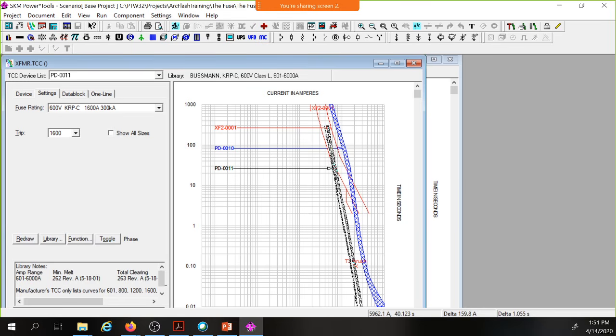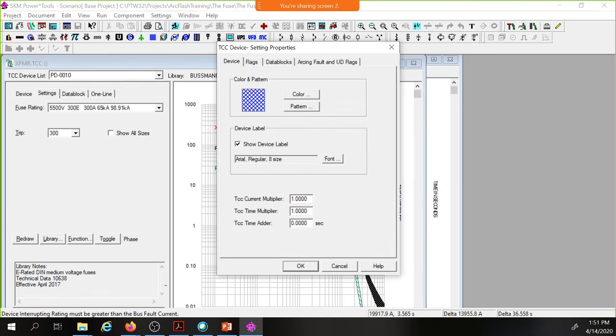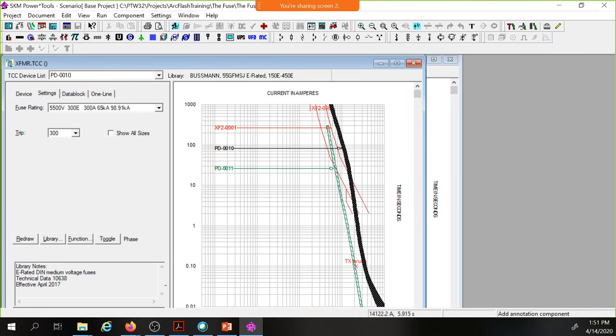I could go with a smaller fuse, but the upper portion of the damage curve on a transformer is really the long time persistent overloads, which are protected by your downstream overcurrent protective device not letting more current flow through the transformer. But again, you have to pick your primary overcurrent devices depending upon which portion of this curve, and we could go into the damage curves for transformers and the IEEE C57. I think it's 37 or whatever.